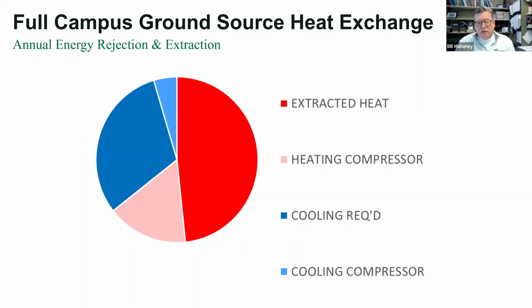I've got to put those ton hours into the ground, right? But I'm also putting in this light blue, which is the compressor heat. So whatever my COP is, let's say I get 3 useful units that I put into the ground, but I also put the compressor heat into the ground, so that puts 4 units into the ground. And so it helps you. It stores more heat in the summer that you can use in the winter.